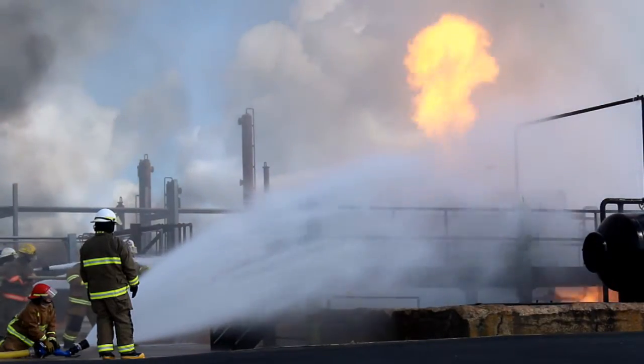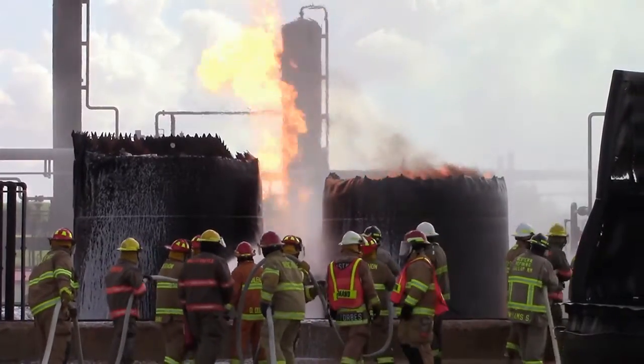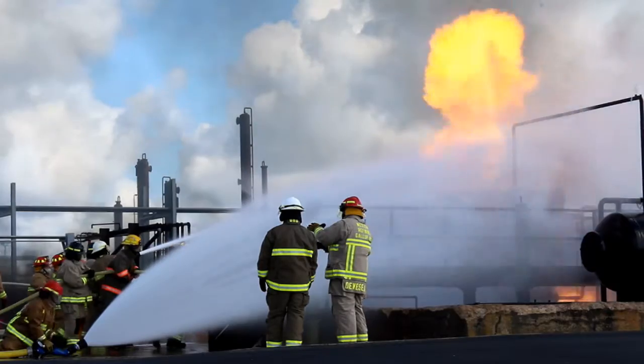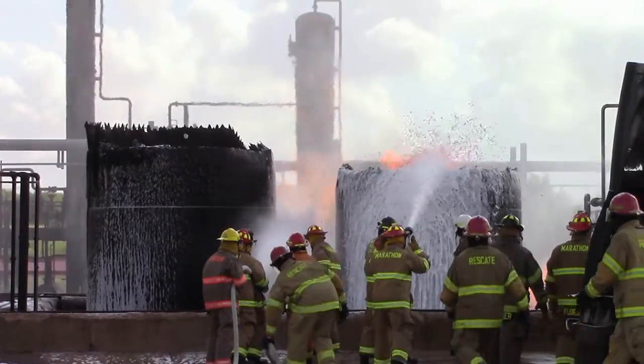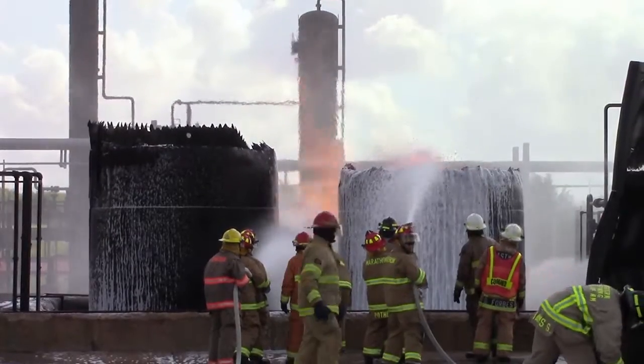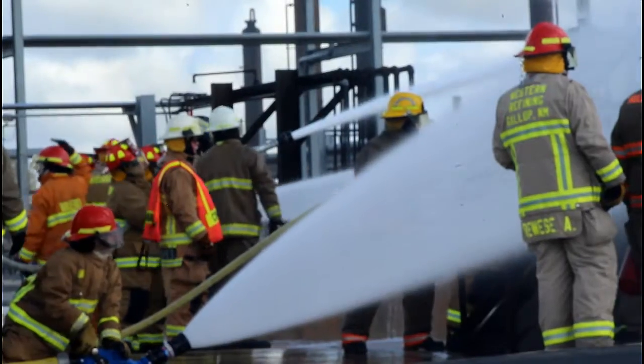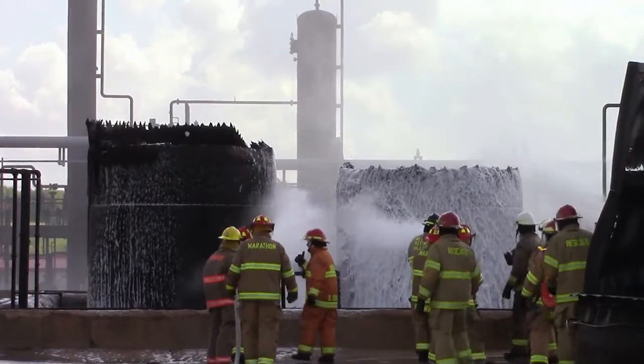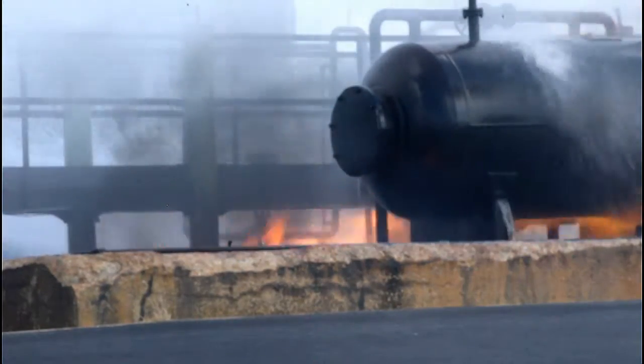When flowing, it's all the way shut right now. This is an air inductor, so I don't need it close to my jacket — I need to be out away from my body, all the way open. On the front there's a deflector plate: open, you get about a 15–20 foot reach; push the deflector plate out and it spews and drops, which is good for a pit fire. But to reach pipes up top, the deflector plate needs to be down before crossing the yellow line. You want finished foam on the tip before you advance.